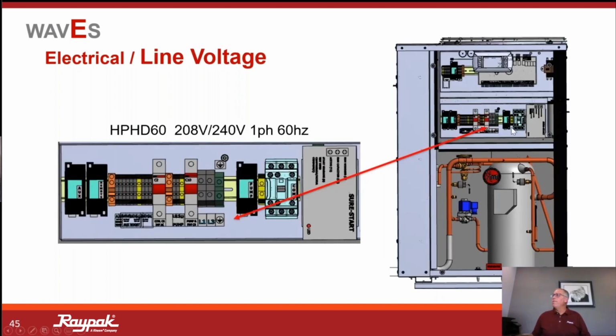So if we remove the covers on the front of the unit, you will see this grid on the 60, the smaller unit, and I've expanded this so you can start to see where we're bringing in primary power. Remember, this is 240 volt single phase, 208 single phase, and this is 60 hertz. Very easy to connect to. Now, on that same unit, I go ahead and talk about the wiring of the circulator. It's a little bit hard to see here, but here's where my pump contacts are, right? And these are dry contacts. So I'm switching power through these dry contacts on out to that circulator.